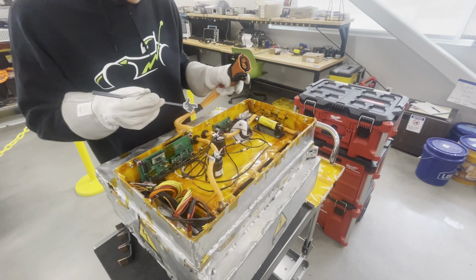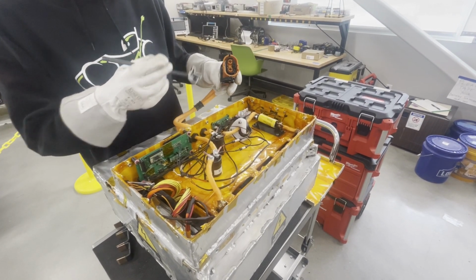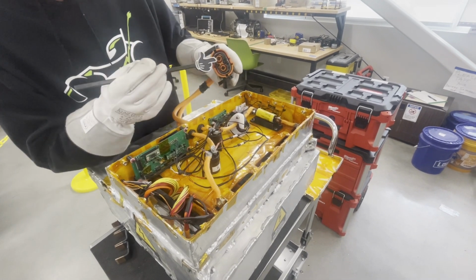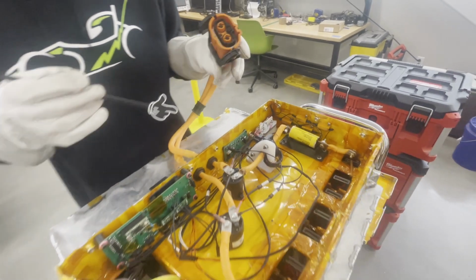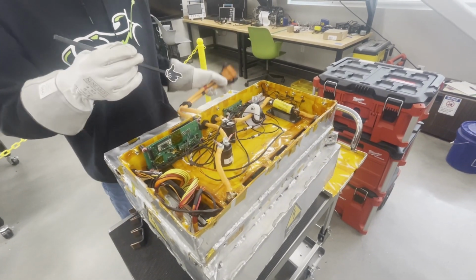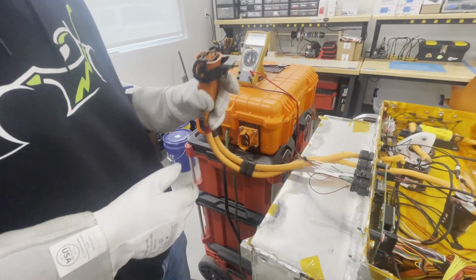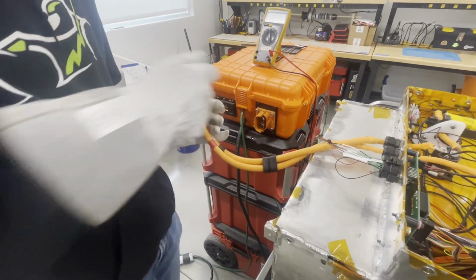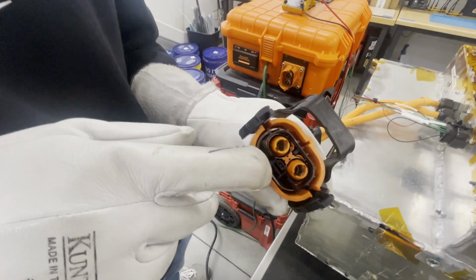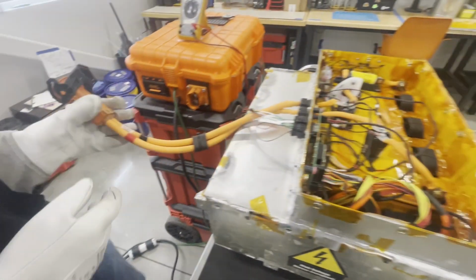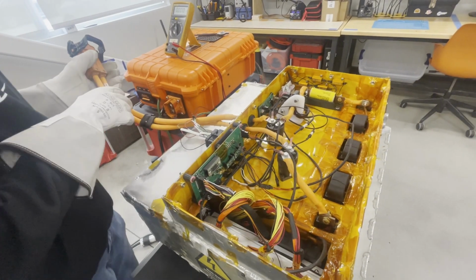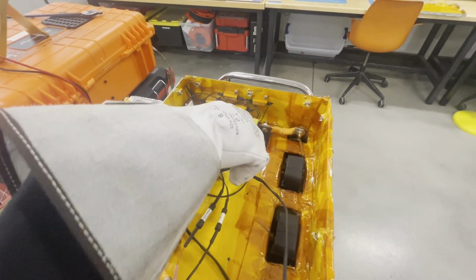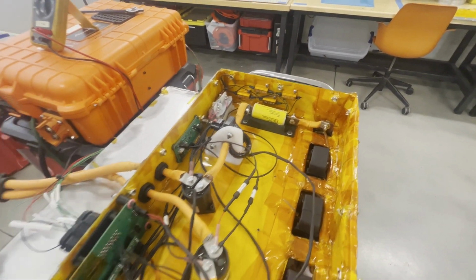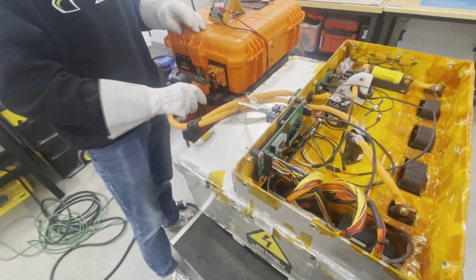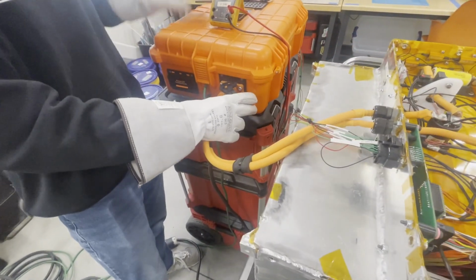As you can see, the only tractive system connector leaving the accumulator housing is this guy, which has an interlock right there that prevents high voltage being present if it is not connected. So here we have our MSD, which connects to our charger. It's the same one as before, so it still has that interlock on it. The high voltage charging leads are still orange, and it is still fused because it's connected to the same circuitry. So what we'll do here is we'll plug this into our charger over here.